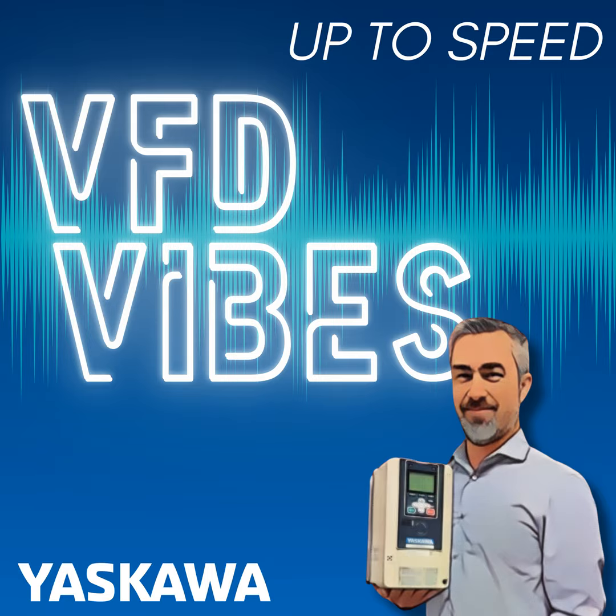And U1-10 has a 1 all the way to the right. Yep, because you didn't have a run command on S1. Okay, I'll get with the controls guy. Maybe he had a broken wire. Maybe the controls wasn't sending the signal, but they thought they were. That's how we would confirm the run command.